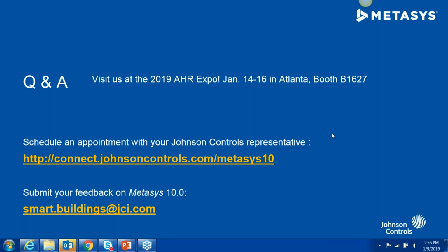Great. And with respect to the new equipment controllers, what type of encryption do they use, and can the wireless capabilities be disabled or removed physically? On the encryption, communications between our engines and the server use web services, and we encrypt those using TLS 1.2 over HTTPS, a secure communication. The BACnet communications between the engines and the controllers use traditional BACnet messaging. Now, the BACnet standard is currently reviewing a new addendum called BACnet SC. Once that becomes an approved standard, we'll be adding that capability to our controllers, and that does provide encrypted, secure BACnet communication at that level.